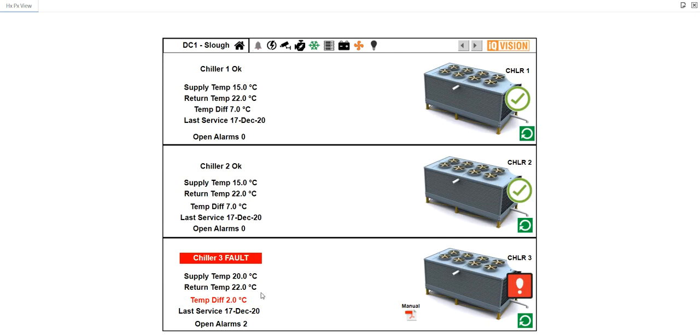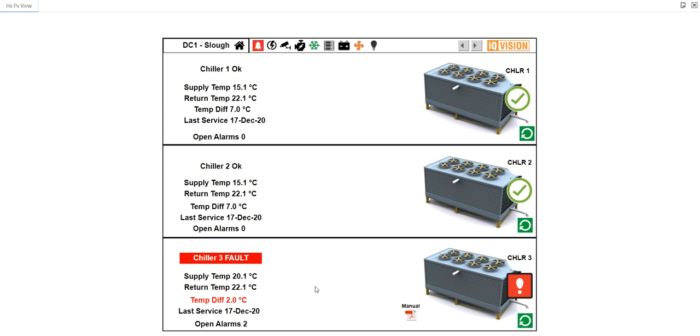You can also see we've used some of the analytics to work out what is going wrong. In red text, the temperature difference between the supply and return temps is surprisingly small, which means the chiller is not operating correctly. It clearly isn't chilling the water down before supplying it. So that will need looking at.